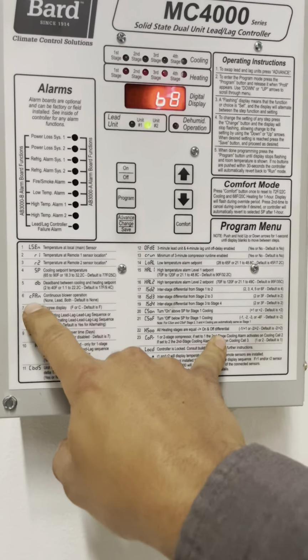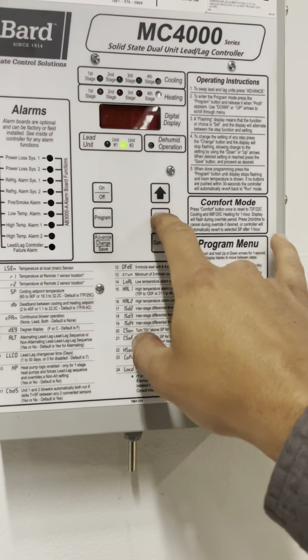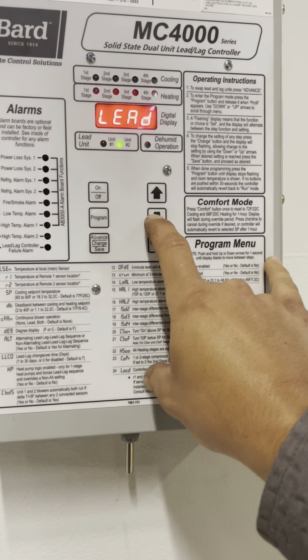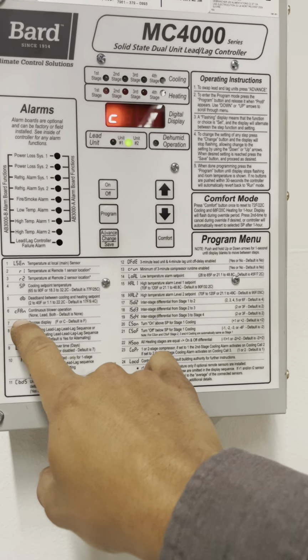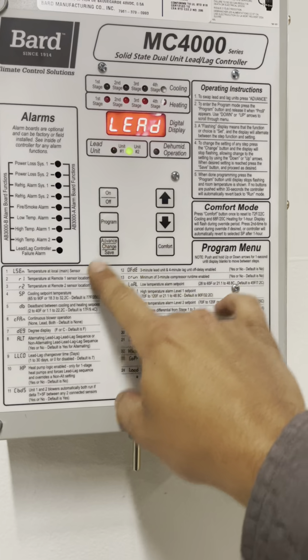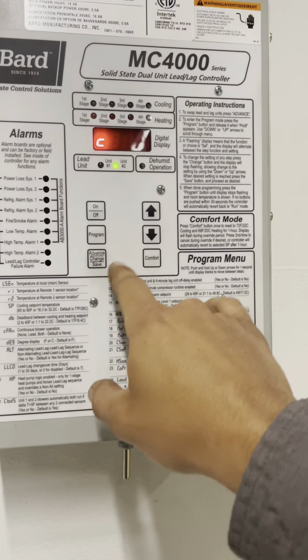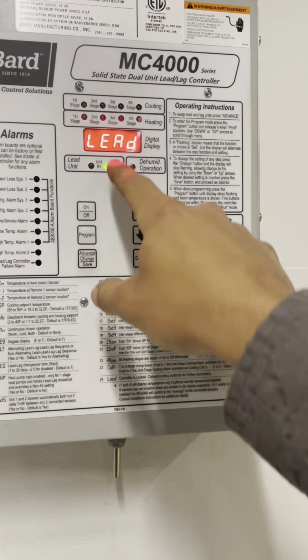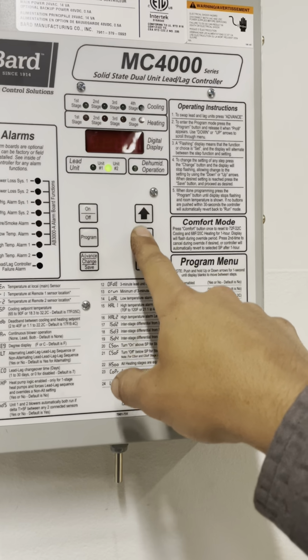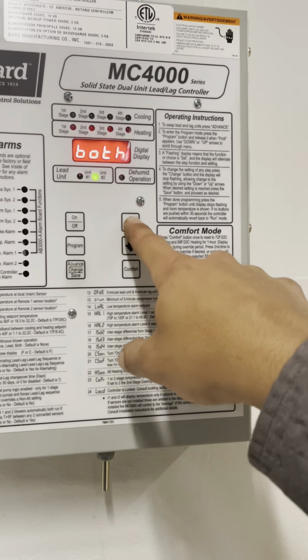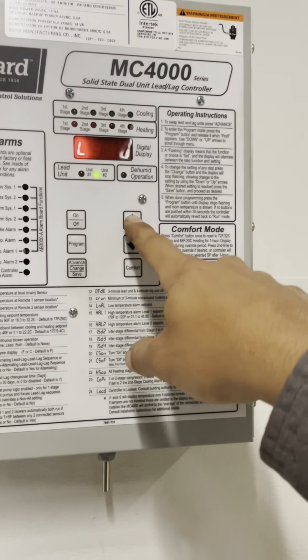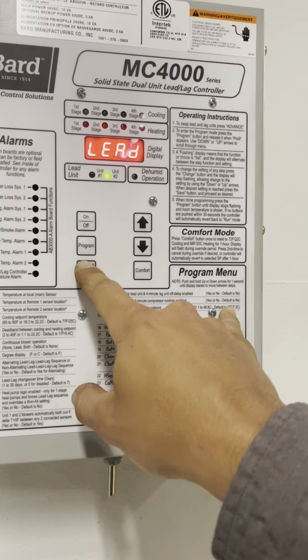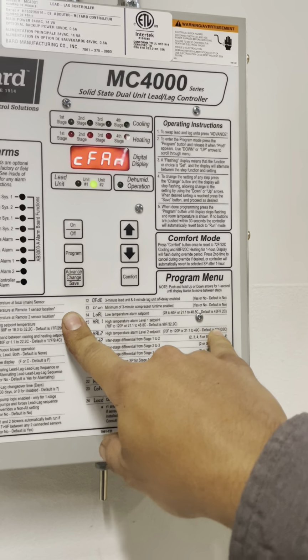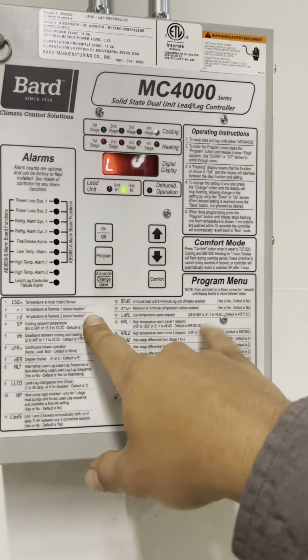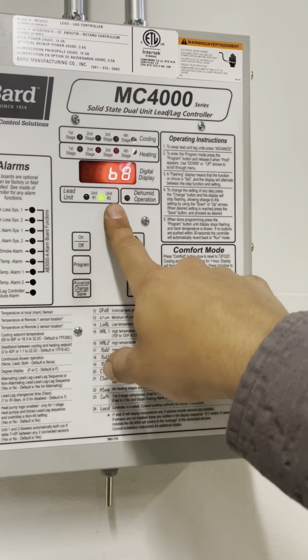Continuous blower operation is C fan. So I think it's this one. It should be set to lead. So let's go to change. Okay, yeah, set to lead. So it's lead, both, or none. So yeah, we want to leave it on lead. So it's right. That fan just probably stayed on, like a time delay or something like that. So now, after I come out of this program mode, I have my set point at 68. I'm at 72, so I should be kicking on.